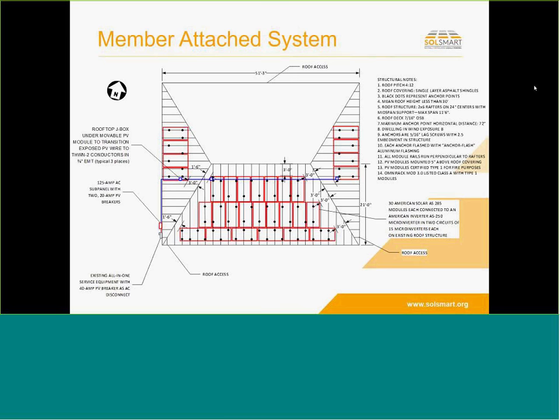It's worth noting that any wire management that you do on that roof has to be sunlight resistant. Otherwise, it'll just rot away in no time. Absolutely. And so you want to look for either nylon 6 or nylon 12, which are the two substances that are the most durable. Nylon 12 we use with galvanized steel, because it turns out that nylon 6 does not work well with galvanized steel. But nylon 6 works fine with the aluminum products that we have, and there are quite a few products out there that are made with nylon 6.